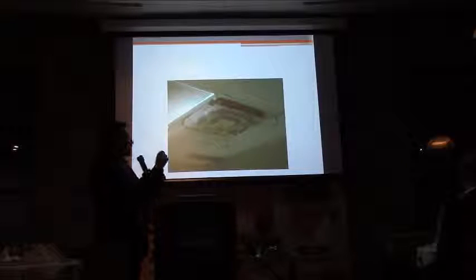So the occupants are comfortable now. But what they don't realize is that they created another problem elsewhere in the system. If you're blocking that diffuser, that air needs to go somewhere. So if that air is coming out from another diffuser, that other diffuser has longer throws, higher static pressure, and higher noise values than anticipated. So you're solving your problem, but you're creating another one elsewhere in the system.